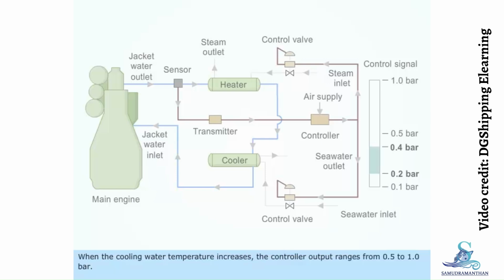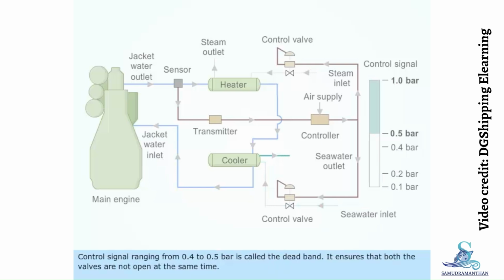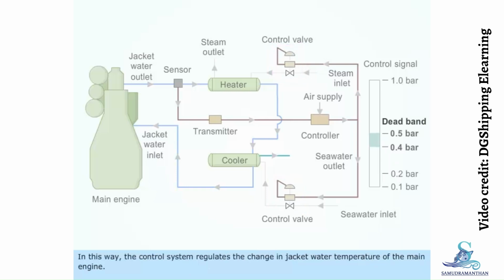When the cooling water temperature increases, the controller output ranges from 0.5 to 1 bar. The cooling water valve of the cooler opens and the set temperature is maintained. Control signal ranging from 0.4 to 0.5 bar is called the dead band. It ensures that both the valves are not open at the same time. In this way, the control system regulates the change in jacket water temperature of the main engine.